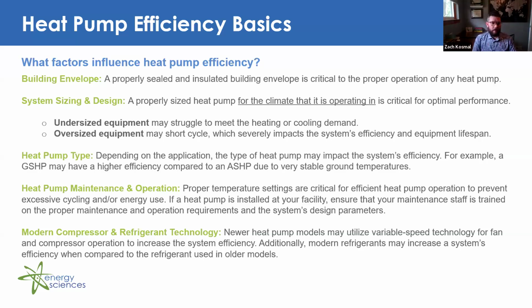In addition to that, heat pumps are meant to operate at a more stable pace as opposed to something like a residential furnace that may cycle on and off very often. So, large space temperature setbacks or setups are not to be implemented during building unoccupied hours because the system is typically not sized or designed to recover from those large setbacks or setups. A modest setback of 2 to 3 degrees can be considered depending on the application.